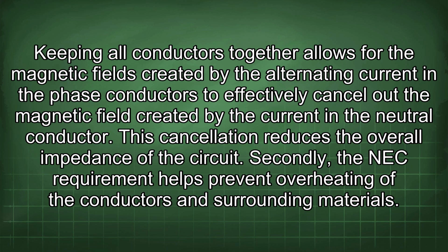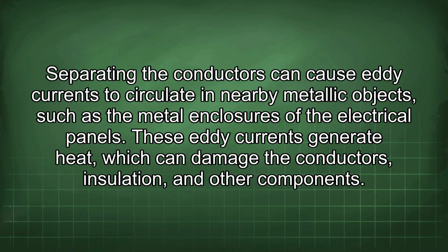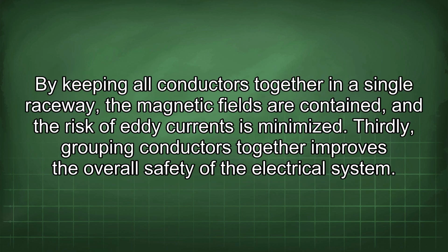Secondly, the NEC requirement helps prevent overheating of the conductors and surrounding materials. Separating the conductors can cause eddy currents to circulate in nearby metallic objects such as the metal enclosures of the electrical panels. These eddy currents generate heat, which can damage the conductor's insulation and other components. By keeping all conductors together in a single raceway, the magnetic fields are contained and the risk of eddy currents is minimized. Thirdly, grouping conductors together improves the overall safety of the electrical system.